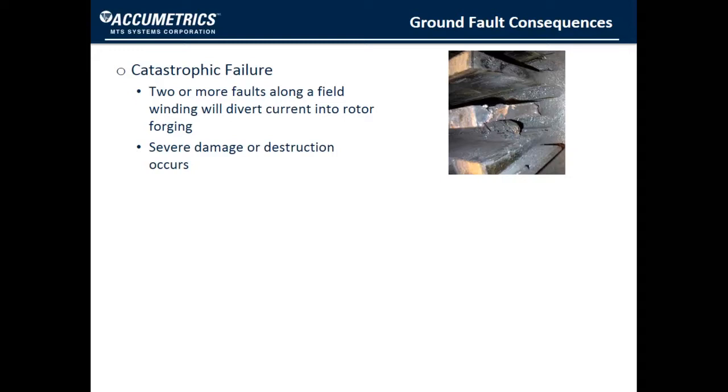In this first photo, we see an example of the slots from a rotor that have been destroyed from the burning of the steel caused by a ground fault where there were two connections.